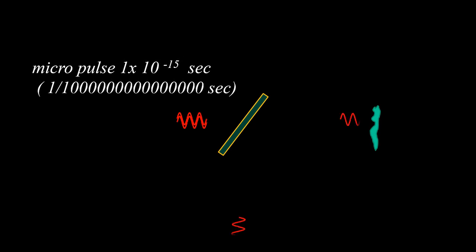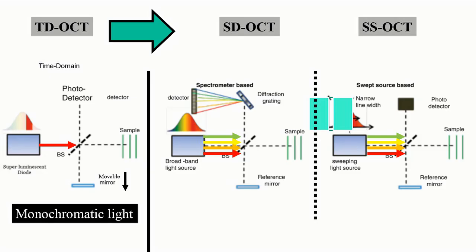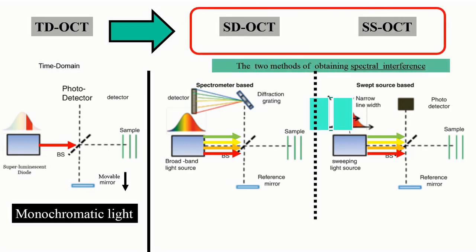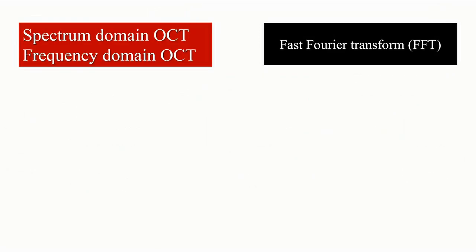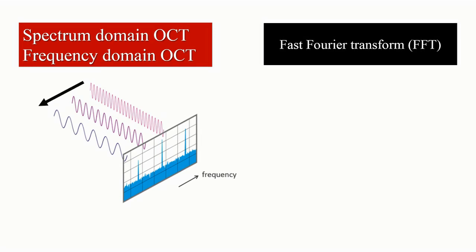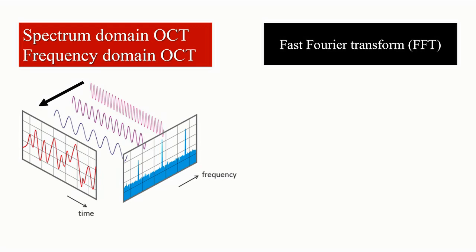Light is pulsed in very small micro-pulses. In spectral domain and swept source OCT, we use broadband light — not a single wavelength, but all bands of light together. Spectral domain depends on the fast Fourier transform, which is why it is also called frequency domain OCT. If we have three waves with three different wavelengths and three different frequencies passing together, the combined result is a complex wave configuration.